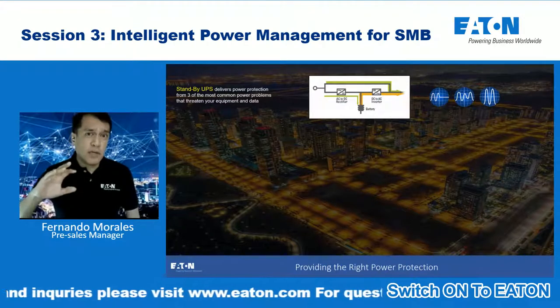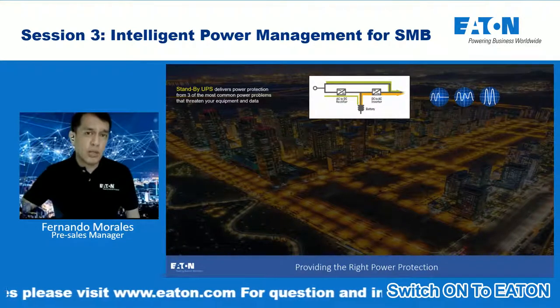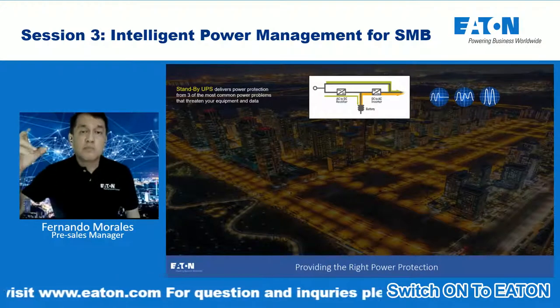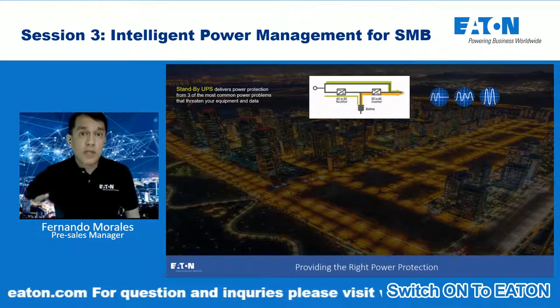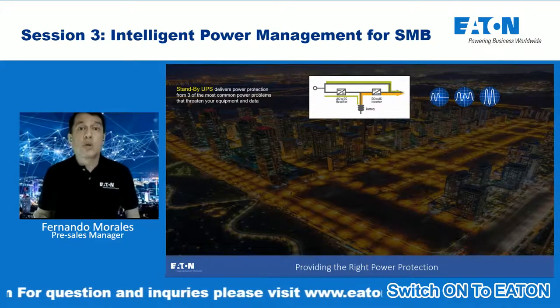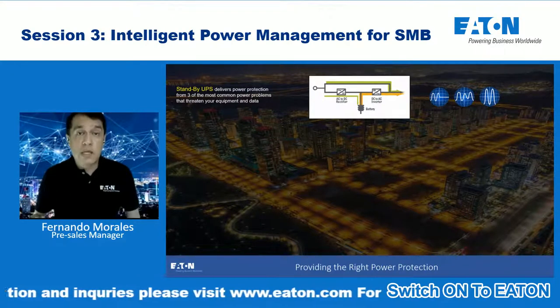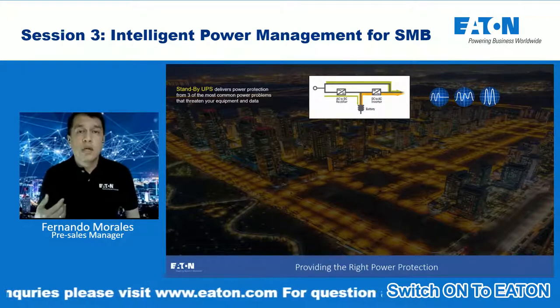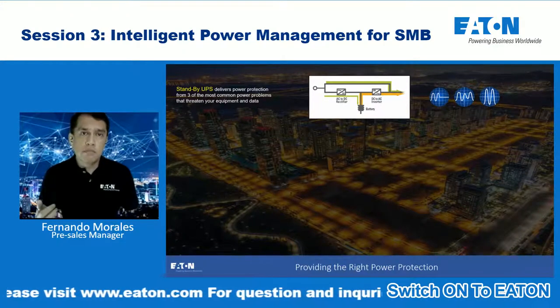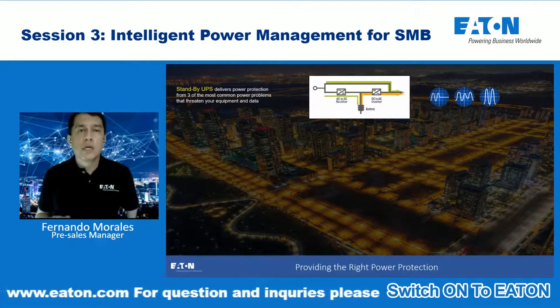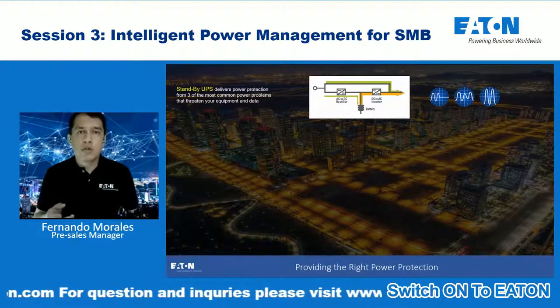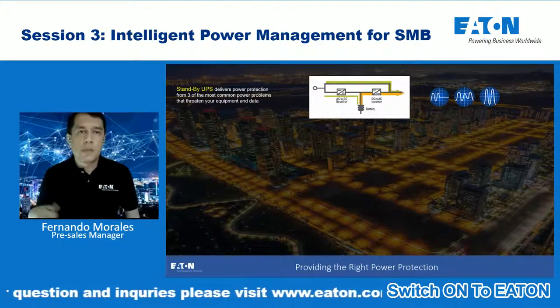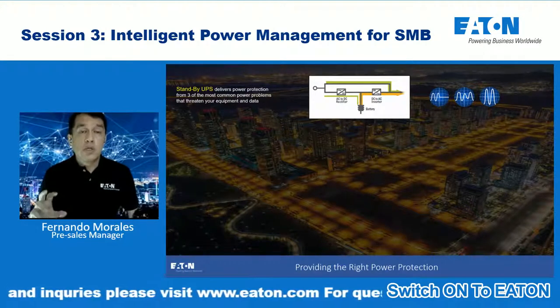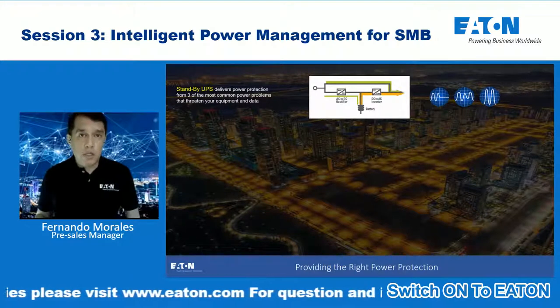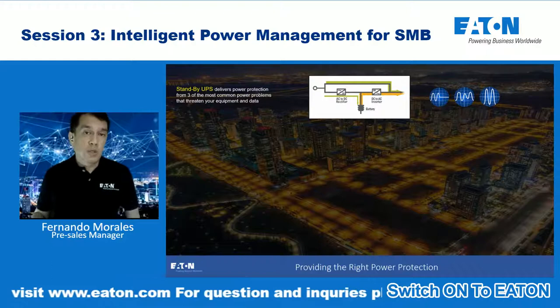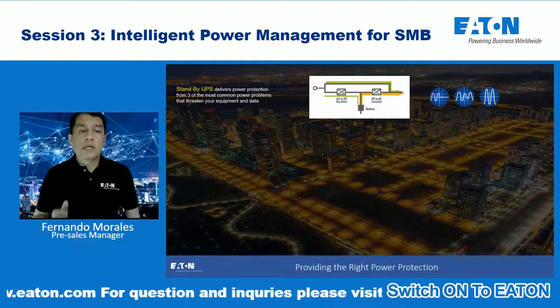If the input voltage supply from the utility goes above these predefined limits, the UPS will shift into battery mode, the inverter will turn on, and then supply regulated power to our loads. If there's a power outage or power failure from the normal operation of the utility feeding the load, the UPS will again shift to battery operation, the inverter will turn on, and supply regulated power to our critical systems.